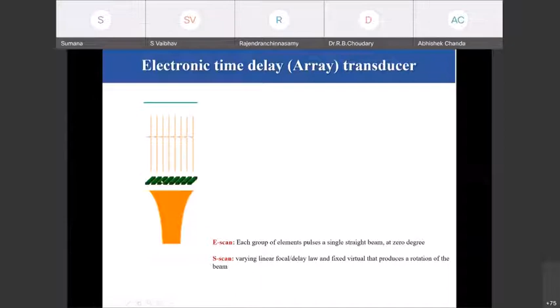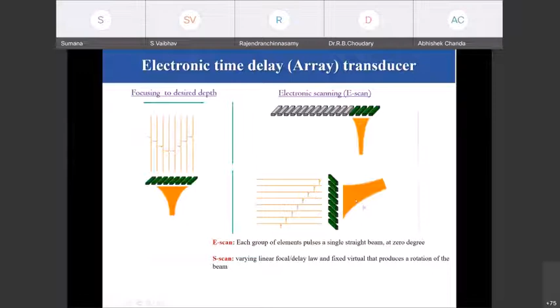In sectorial scan, this is another method, which is also called azimuthal or angular scan, and the beam is swept through a particular angle using the same active group of elements, or it can be electronically moved till the last element within the probe. And here focusing and steering are also done simultaneously. So in weld material inspections, mainly sector scan is used.